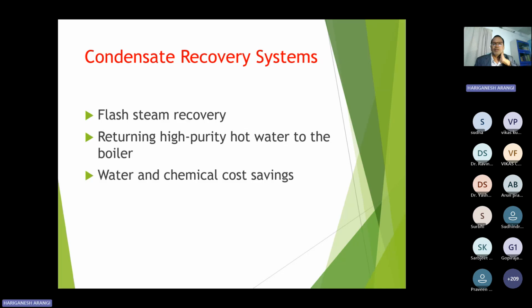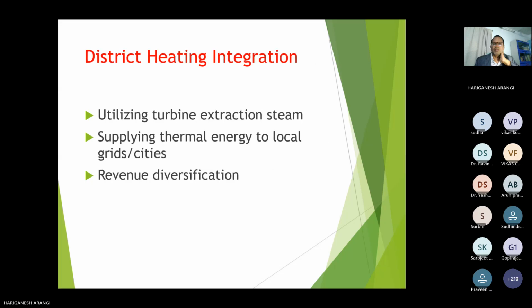Condensate water recovery also, like the drain systems. Normally, sometimes the drains are thrown into the atmosphere or out of the steam zone area. Without wasting that steam, it can be recovered through flash systems, like drain water atmospheric flash tanks. Through that, water can be recovered. And heating integration also, utilizing turbine extraction steam, supplying thermal energy to local grids, revenue diversification.